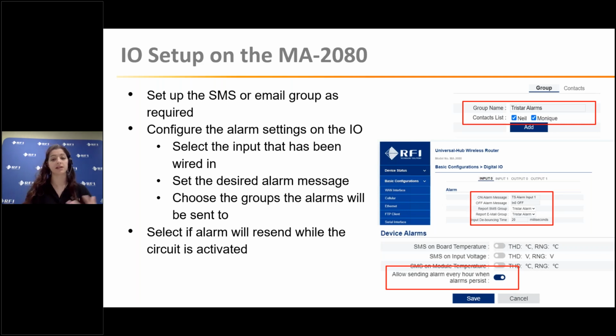From there, you look at the setup for the basic configurations of the I/O themselves. You're able to customize a message, which is a really nifty feature in the MA2080 - not all I/O allows for customizable messages. This means we get something more exact than just saying I/O 0 has been triggered; we're able to use up to a certain number of characters in a single text message. In this case, I've said TriStar alarm input 1, so we get more context for the message sent out, making it easy to be interpreted by people, not just machines.